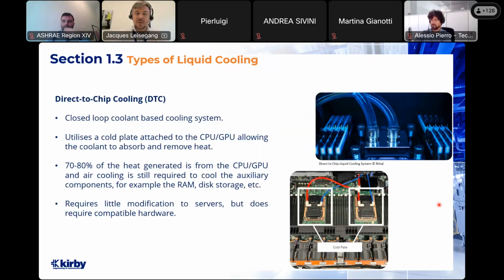cooling solution. So it's important to understand that a direct chip cooling system is a hybrid system. It has an element of liquid cooling, but it still needs that element of air cooling. The benefit of this system is that it requires little modification to the servers, but it does require compatible hardware.